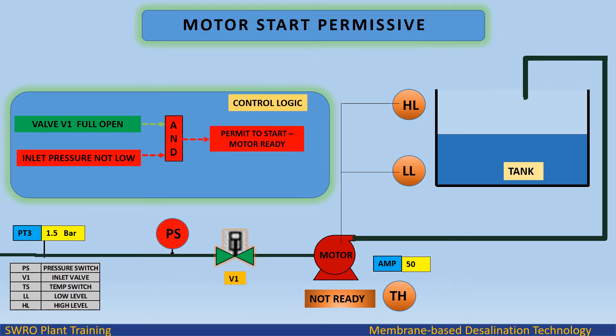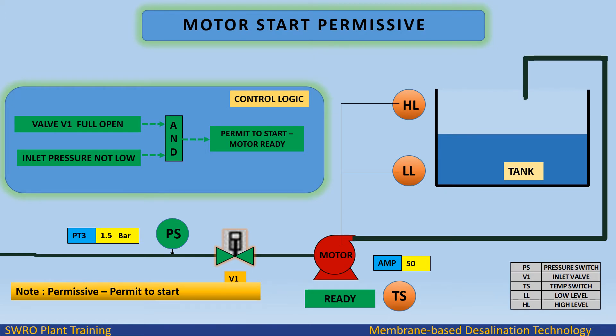Motor start permissive control logic example: if valve V1 is full open but inlet pressure is low, permit to start motor is not ready. However, if valve V1 is full open and inlet pressure is not low — both pre-conditions satisfied — then permit to start motor is ready.